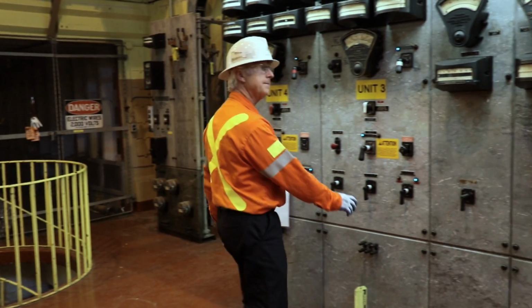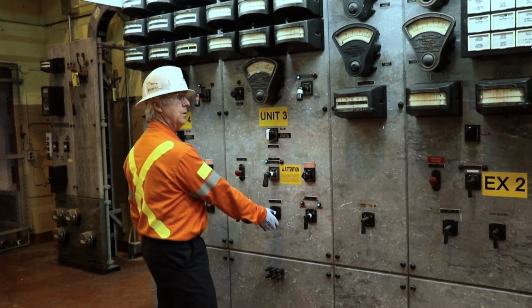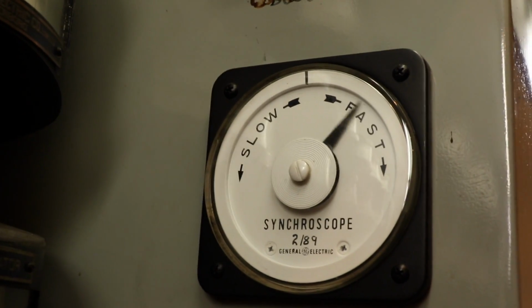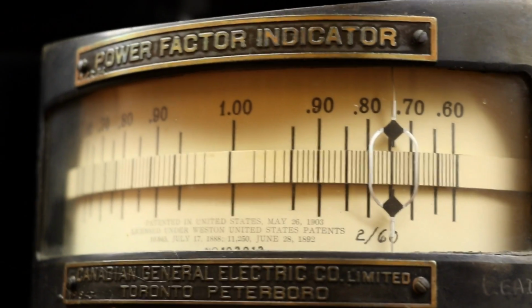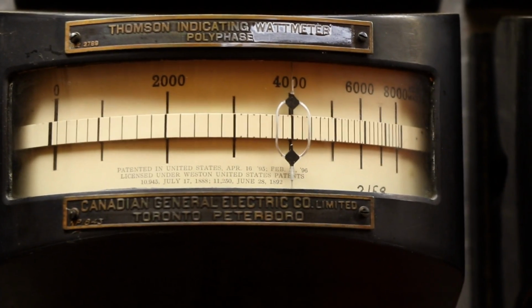This unit has to be manually synchronized online, which is unlike our remotely controlled units. The proper voltages and power factors need to be loaded onto the unit to achieve the desired megawatt output as directed from our system control center. As I said before, the equipment involved is old and sometimes unresponsive. This only adds to the risk when operating.